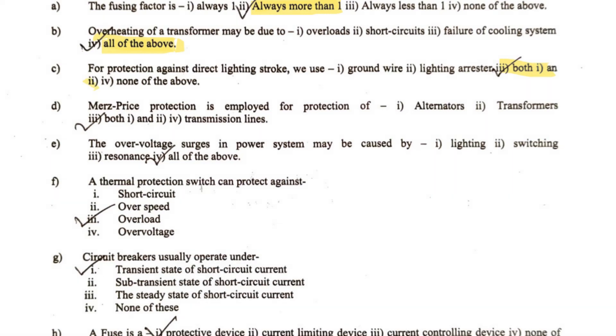The next question: Merz-Price protection is employed for protection of what? Merz-Price protection is basically the differential protection scheme. This type of protection scheme is generally used for the transformer as well as the alternator, protecting them against internal faults like inter-turn short circuits and other kinds of short circuits or arc faults. So option three — both one and two — is the correct answer, meaning Merz-Price protection is used for protecting both alternators and transformers.